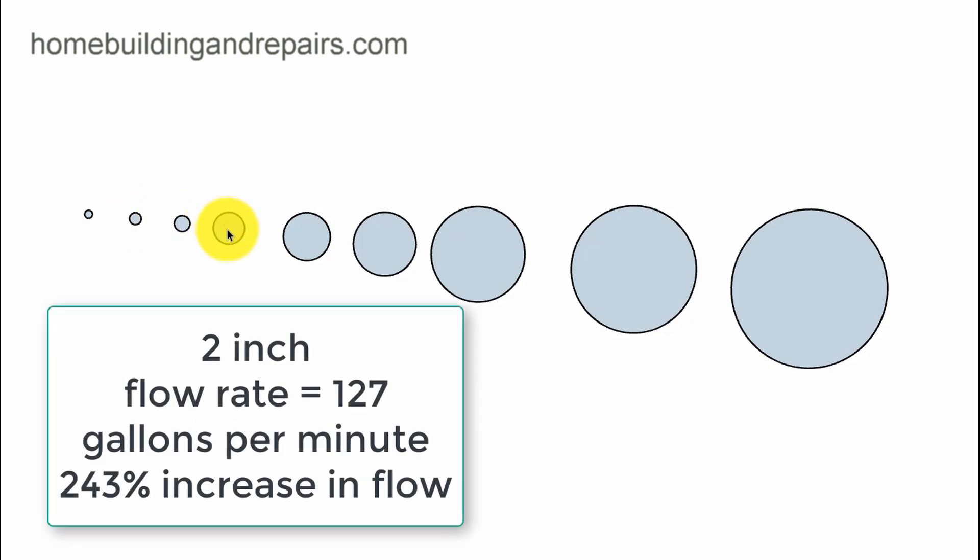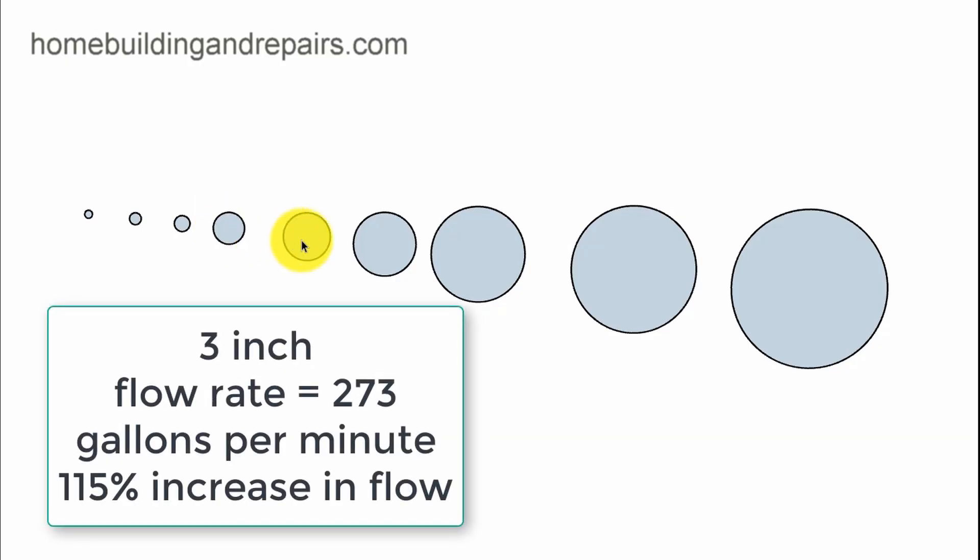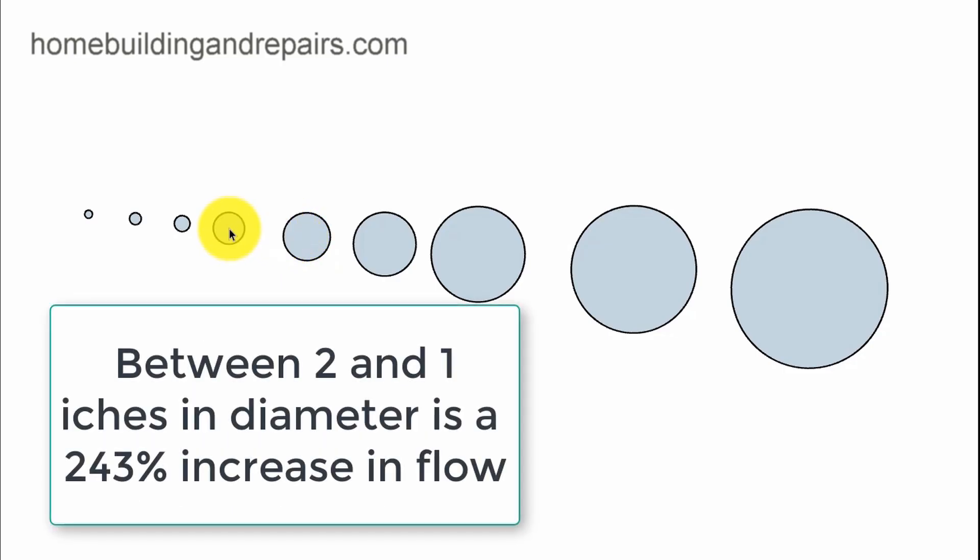Once we go to a 2-inch pipe, we are now increasing the amount of volume from a 1-inch to a 2-inch by 243%, or 127 gallons per minute. When we go to the 3-inch pipe, it's 273 gallons per minute. Remember, we're working with their PSI measurement. You increase the PSI or you lower it, you're going to get different numbers. But the difference between these two is now 115%. The biggest increase so far was between the 2-inch and the 1-inch pipe.